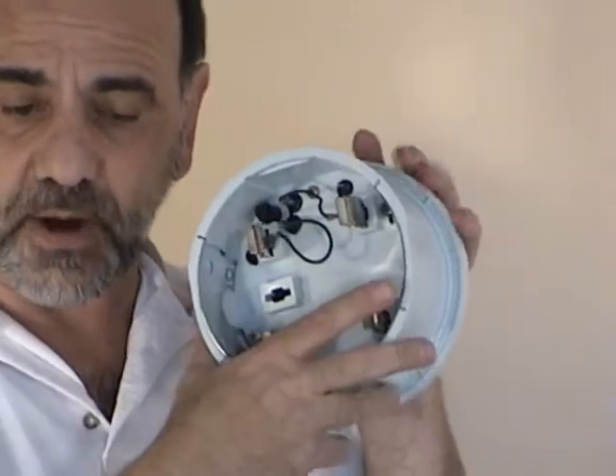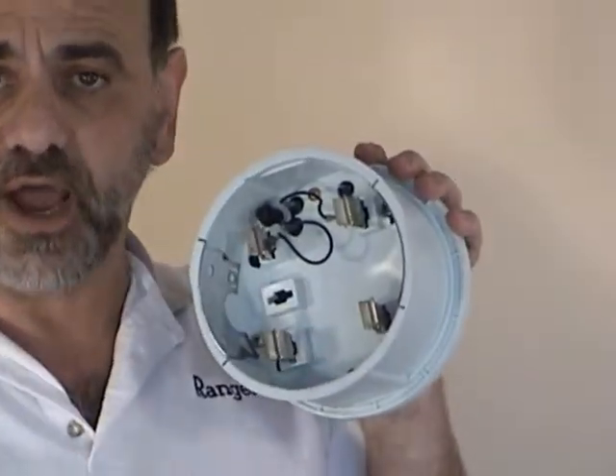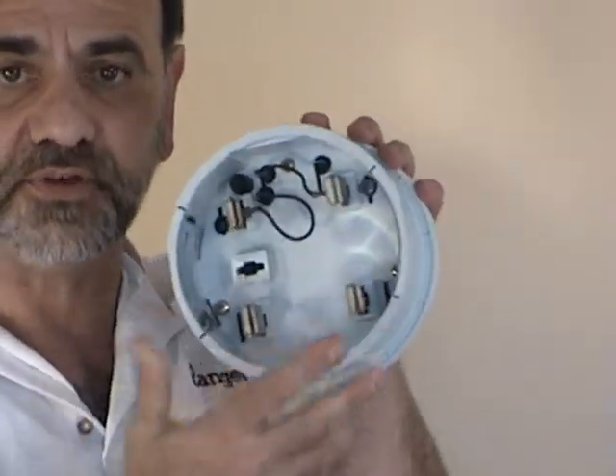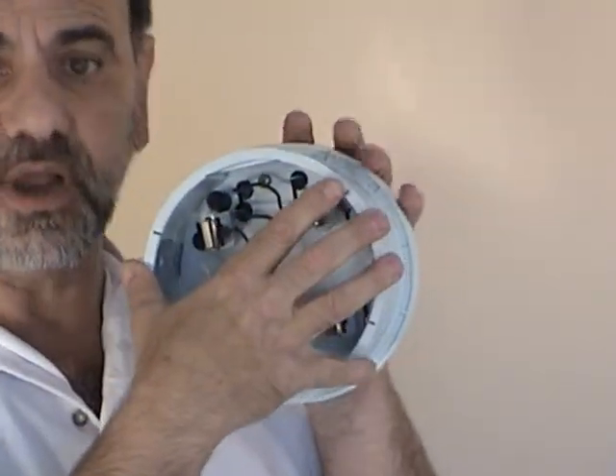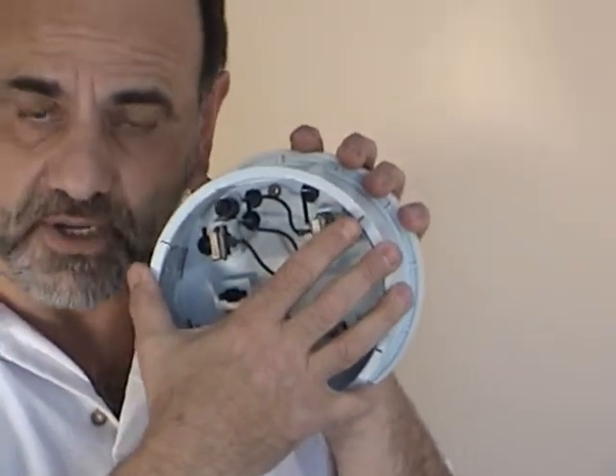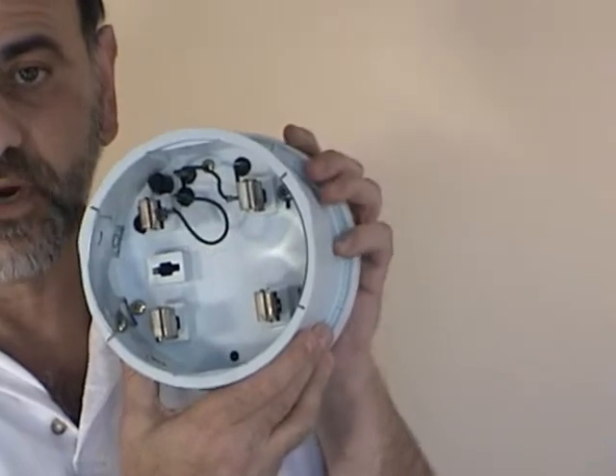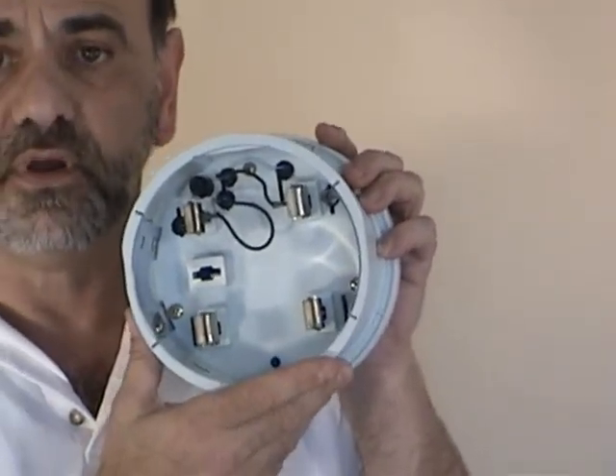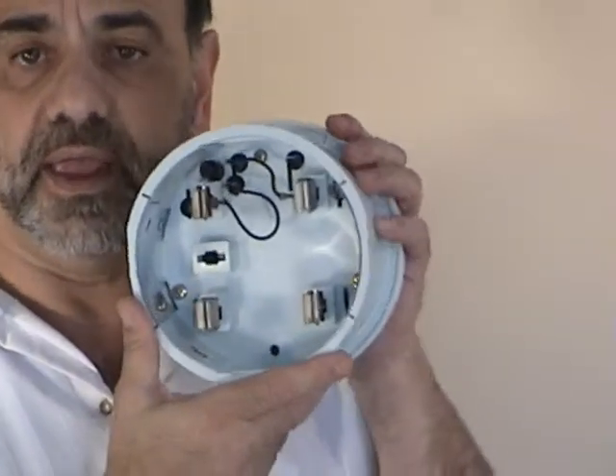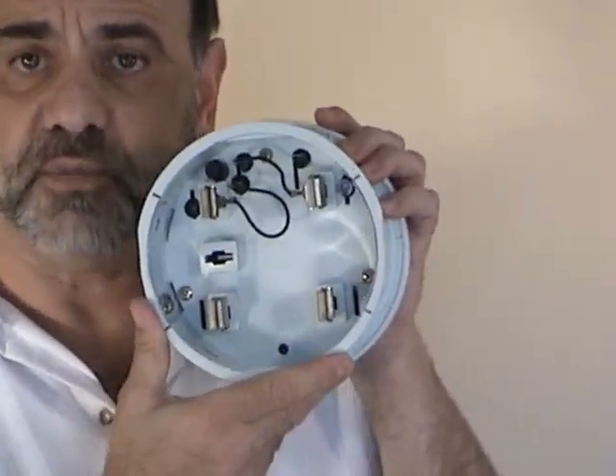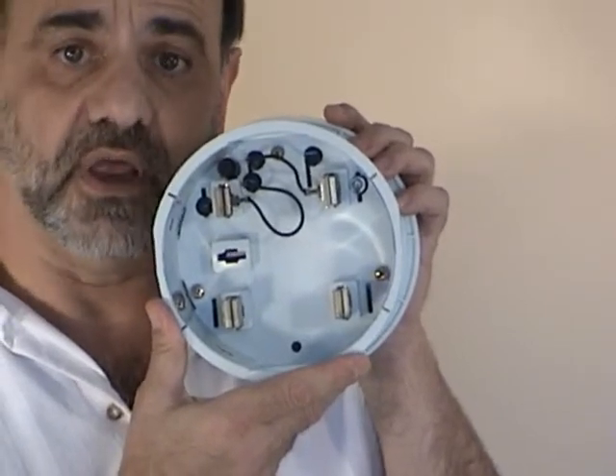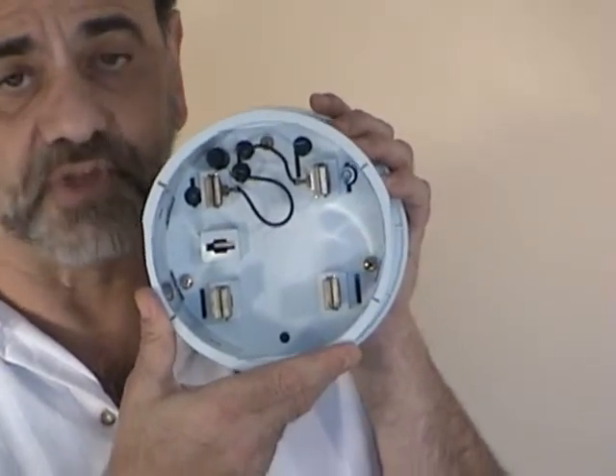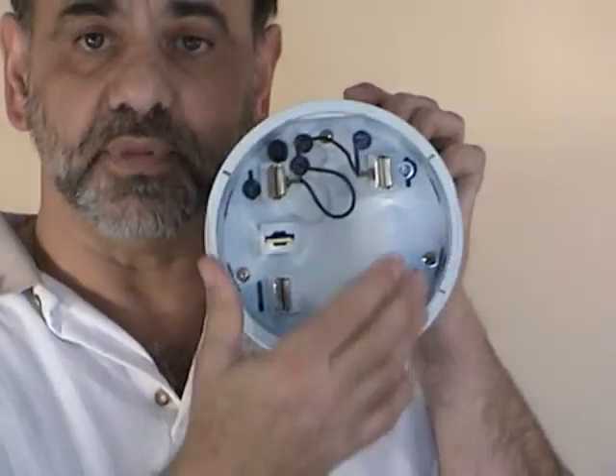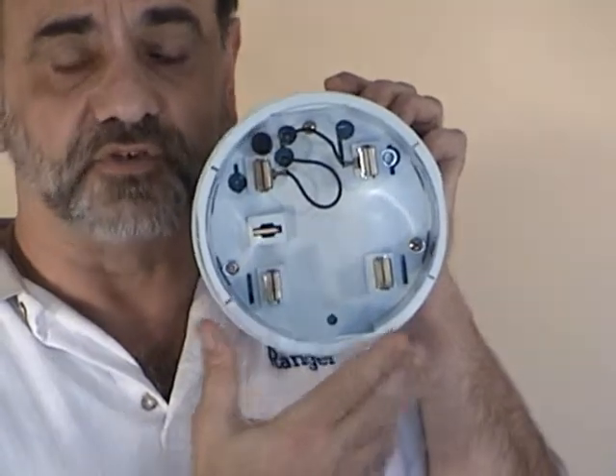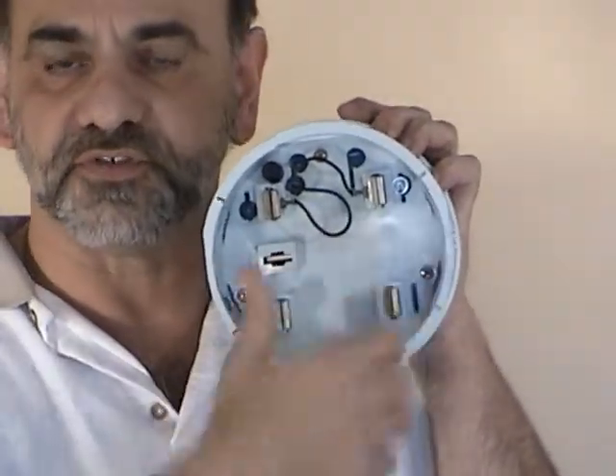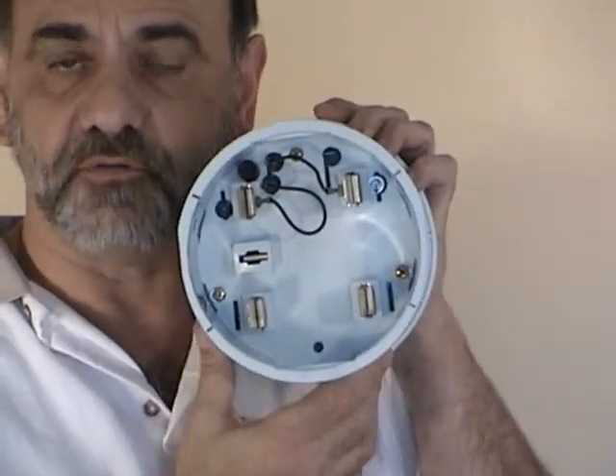The power company will remove the meter off of the house. They will then place this in place and return the meter to here, and then it will automatically start logging. The conditions that the unit will automatically start logging under is if it sees a voltage from L1 to neutral and it doesn't see any current load at all. After 15 minutes it will begin to log anyway. If it sees as small as 100 milliamp current load, which is almost anything in the house, it will then begin logging in 1 minute. So there's no buttons in here that you have to remember to push to start it before you go or anything like that. It will start itself automatically logging.